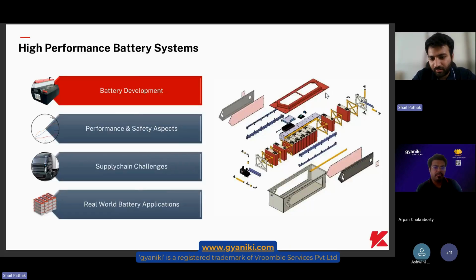Here I have an image of the entire exploded view of a battery system. Now, immersion cooled batteries use only liquid immersion as their cooling or thermal management system. You can see on the right hand side and left hand side of the image that there are cassettes placed, and a pump is also placed for circulation inside. So this immersion fluid, when circulated through natural and forced convection, dissipates heat from the hot spots to the casing, and from the casing there's a reaction that happens where the heat is dissipated outside. So we have a multi-phase cooling system on the casing.